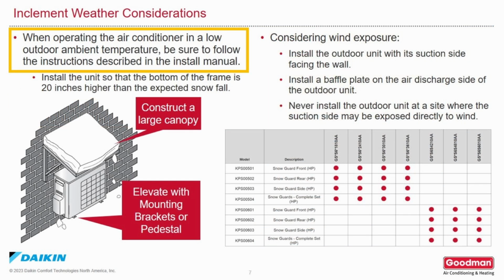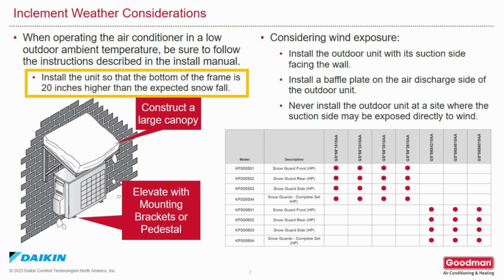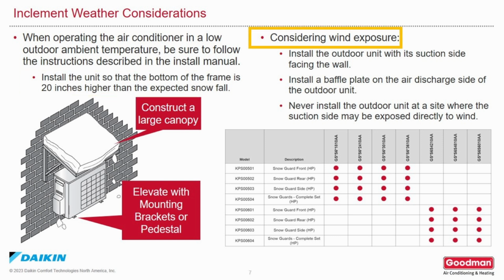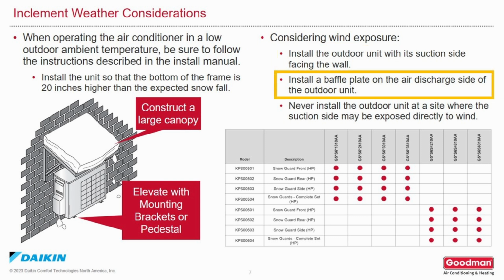When the system is installed in a location that has a possibility of operating in a low ambient temperature condition, be sure to follow the instructions in the installation manual. Install the outdoor unit so that the bottom of the frame is at least 20 inches higher than the expected snowfall. Also, consider wind exposure so that the inlet air side of the coil is always facing the wall, and then, when necessary, install a wind baffle on the discharge side of the outdoor unit. Never install the outdoor unit where the inlet side is exposed directly to the wind.